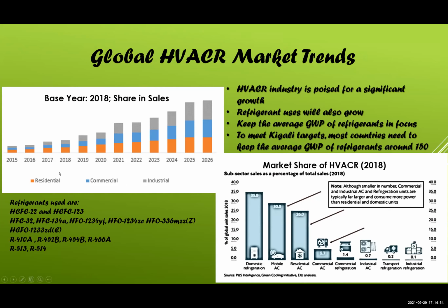And 123 in centrifugals is still there, but there are new refrigerants which have come in. And then you have 32, 134A, 1234yf, 1234ze, 1336mzz. Then we have HCFOs. This is a little bit of a controversy because it is still a hydrochlorofluoroolefin. That means its ozone depletion potential is not zero, but it's close to residual zero.